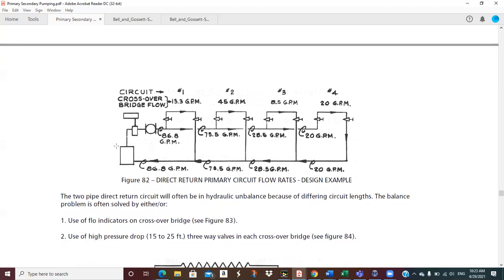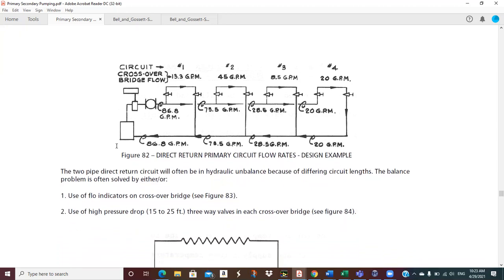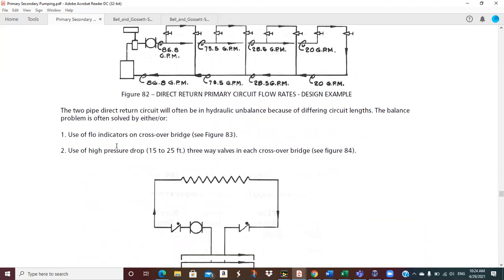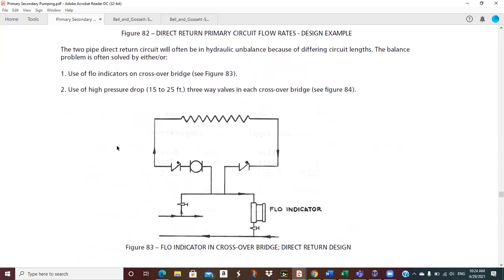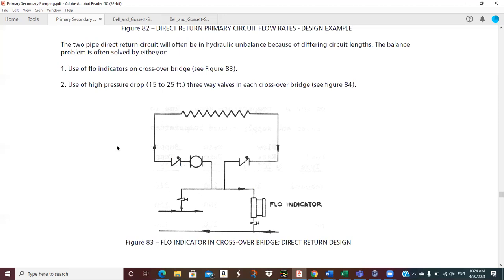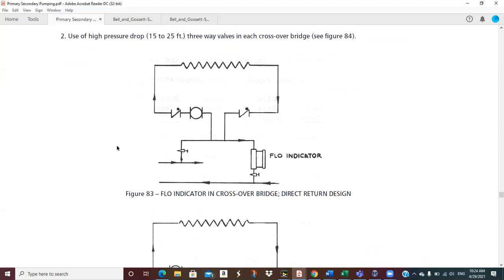Now he's talking here, okay, what if you did this with a direct return? If you did this with a direct return, you would potentially be looking at some significant imbalance depending on the coil pressure drops. So he says some things you can do. You can put a flow meter indicator in the crossover. That's supposed to help. He recommends both of these.